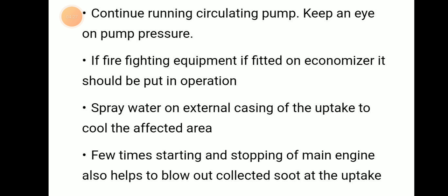A few times starting and stopping of the main engine also helps to blow out collected soot at the uptake. Continuous running of the circulating pump should be maintained. If firefighting equipment is fitted on the economizer, it should be put in operation and water sprayed on the external casing of the uptake to cool the affected area.